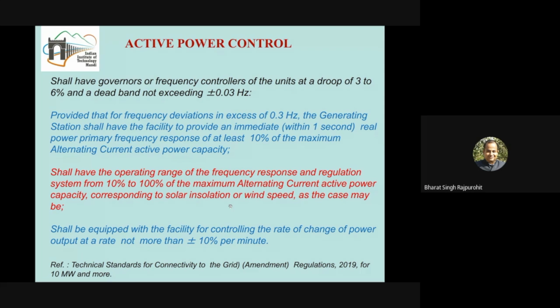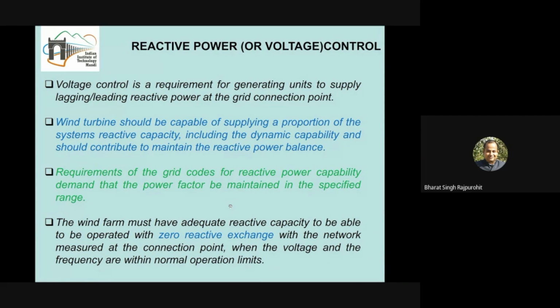But now the question is whether it is possible for the SPV or the wind turbine to increase the output by 10%. This is an important question for the technology. So my suggestion is, why not always operate somewhere 10% lower than the maximum power point tracking algorithm, whether it is SPV or a wind turbine, so that some margin is available which can be increased if there is demand based on the frequency deviation. Then similarly, some other controlling limits are also prescribed here. Okay, now again coming back to the reactive power control.